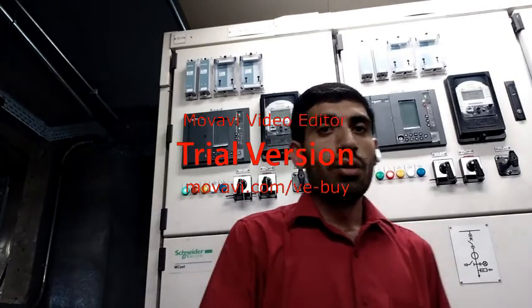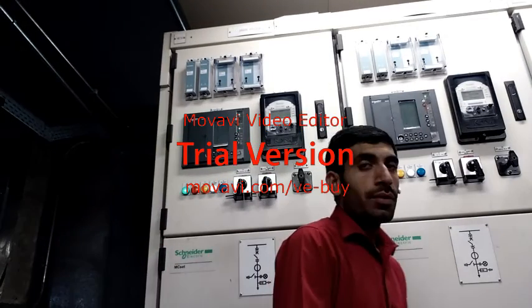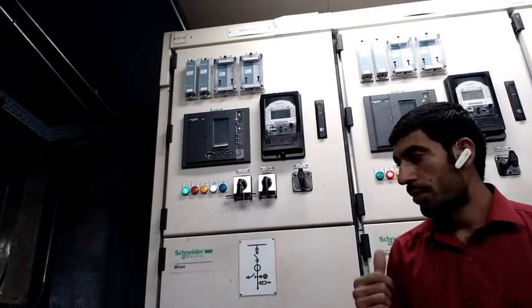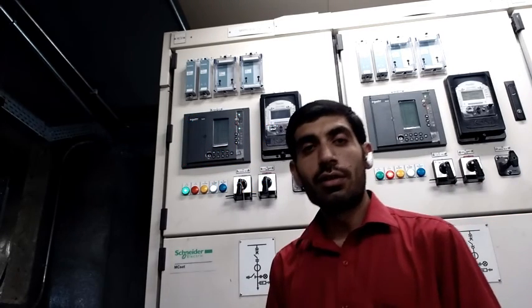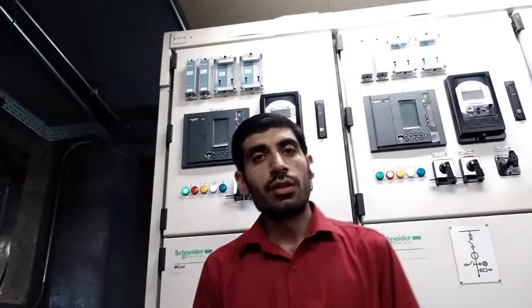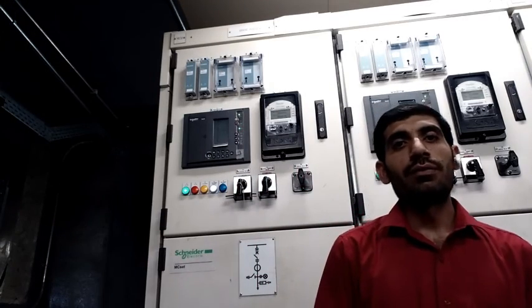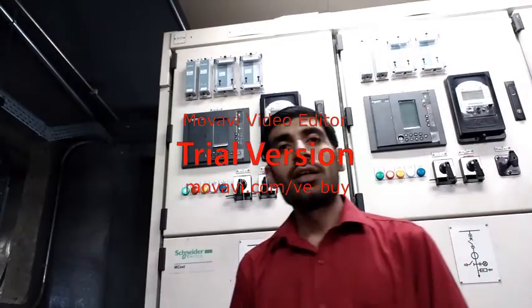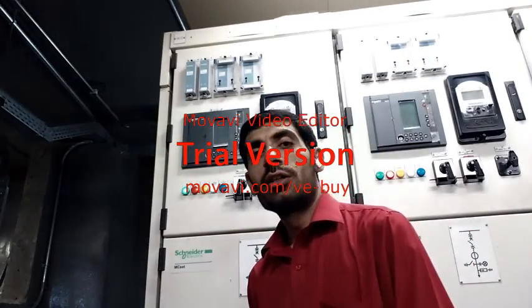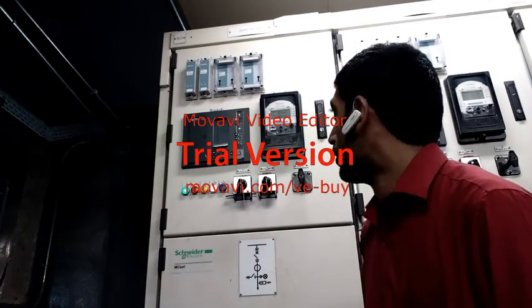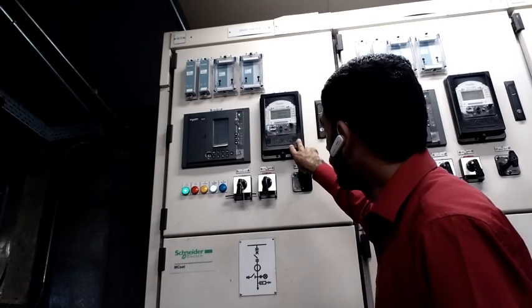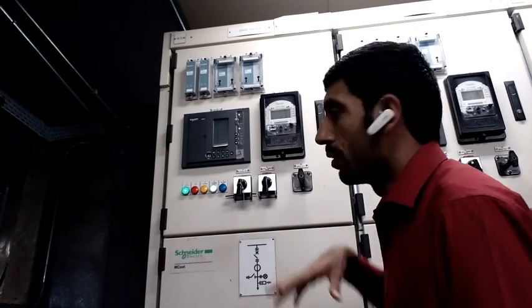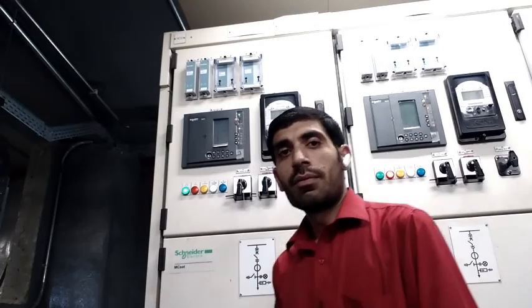So we take the voltage loop from the bus metering VT. The bus rated voltage is 13.8 kV, and the VT ratio is 13.8 kV to 115 volts. The primary side is 13.8 kV and the secondary side is 115 volts. That 115 volts comes into this multifunction meter, and we can see these values here on this multifunction meter.